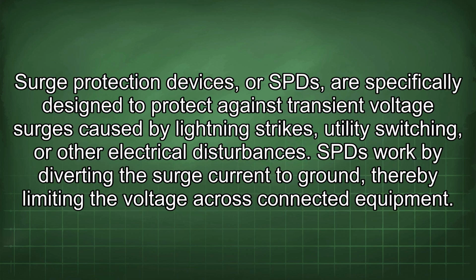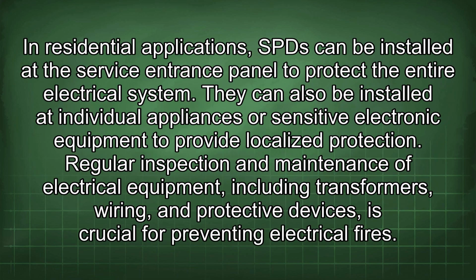Surge protection devices, or SPDs, are specifically designed to protect against transient voltage surges caused by lightning strikes, utility switching, or other electrical disturbances. SPDs work by diverting the surge current to ground, thereby limiting the voltage across connected equipment. In residential applications, SPDs can be installed at the service entrance panel to protect the entire electrical system. They can also be installed at individual appliances or sensitive electronic equipment to provide localized protection.